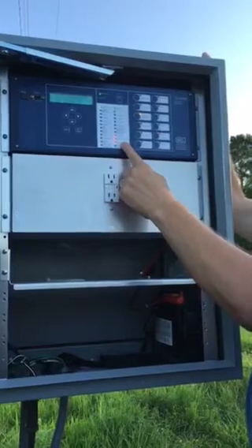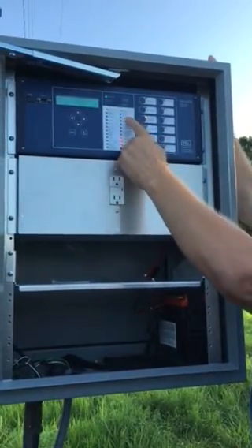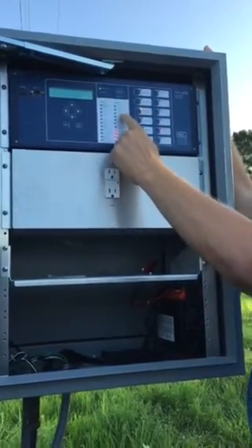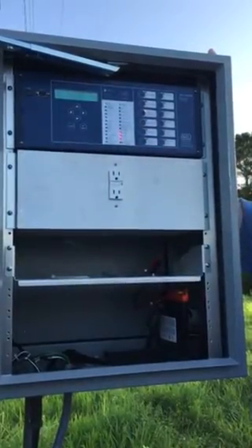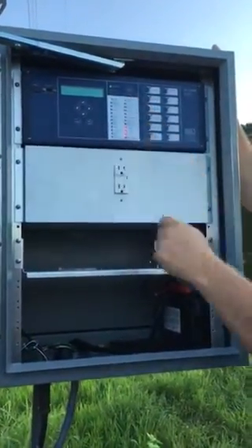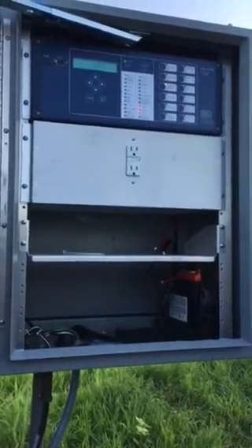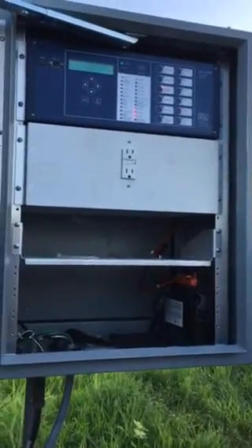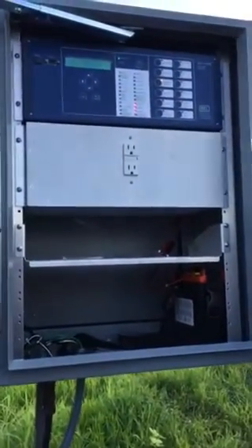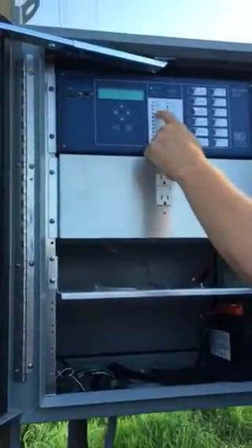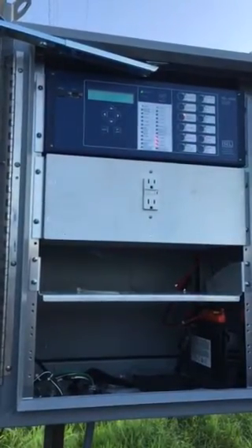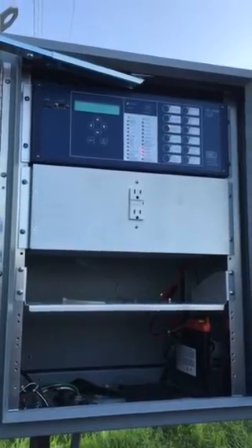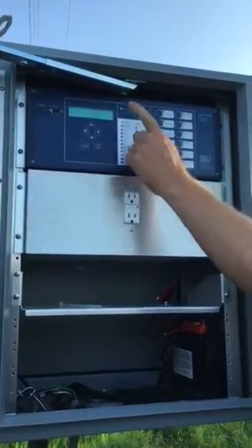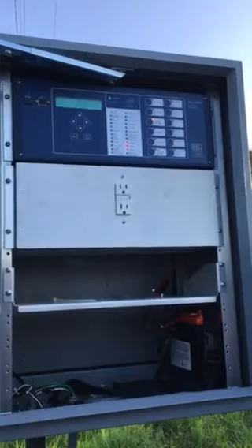You're going to see these three phases close in, but it's going to be about 15 seconds before these lockout lights go away. And when they do, the reset comes back on. That's checking to see if there's a fault on it to open back up before it resets. Now, it should never be a fault, because if these fault lights are lit up, you won't close it in. You can't close it with a push button, you can't close it by SCADA. All you have to do is hit the target reset. If they clear, then you can close it.